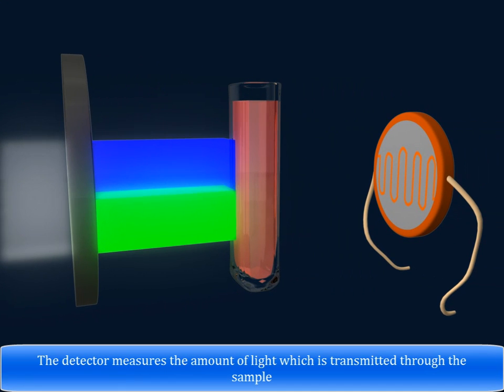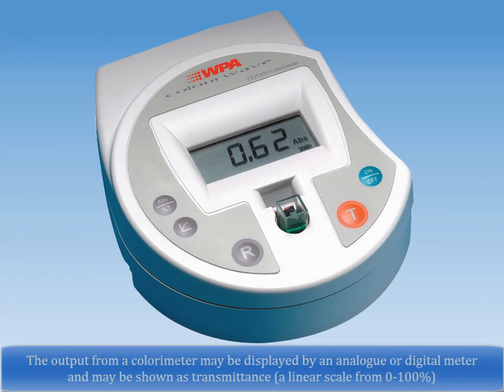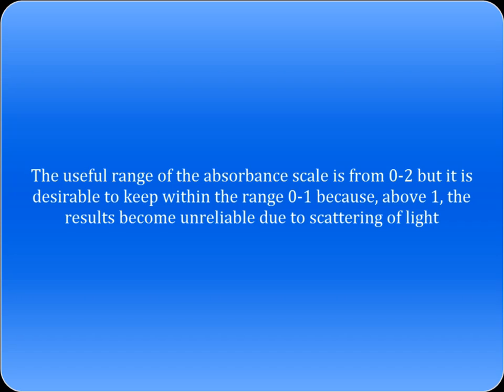The detector measures the amount of light which is transmitted through the sample. The output from a colorimeter may be displayed by an analog or digital meter and may be shown as transmittance, i.e. a linear scale from 0 to 100%. The useful range of the absorbance scale is from 0 to 2, but it is desirable to keep within the range 0 to 1, because above 1, the results become unreliable due to scattering of light.